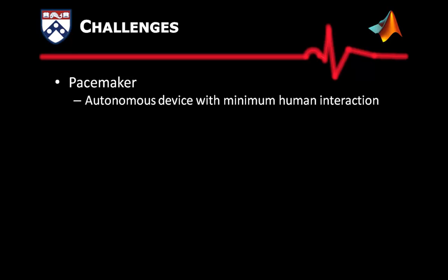The pacemaker is a typical cyber-physical system. There are several challenges for developing safe software for the pacemaker. The pacemaker is an autonomous device and there is very little human interaction once the device is implanted. This means the device has to be able to operate under all possible heart conditions without causing catastrophic failures. A pacemaker has only two to three leads inside the heart which sense local electrical events, so its diagnostic capability is very limited. The pacemaker may be confused when two distinct heart conditions have the same input sequence. With the same leads, the pacemaker can deliver electrical pacing which can only increase the heart rate. These limited capabilities make evaluating the pacemaker performance very difficult.